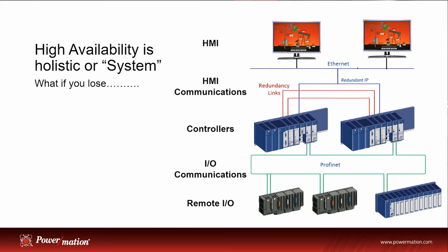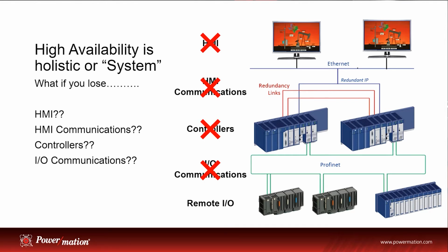So the first would be in a system is like redundant communications to a process, right? So you've got an operator interface, you're watching the machine run. What happens if that operator interface is lost? Can the machine run by itself? Can that tunnel, can that barn cool the birds or give the people oxygen without an operator sitting there pushing the buttons? That's an important piece. So you're saying if we do need an operator, maybe that's a situation where we need to have redundant communication networks or maybe even a redundant HMI.